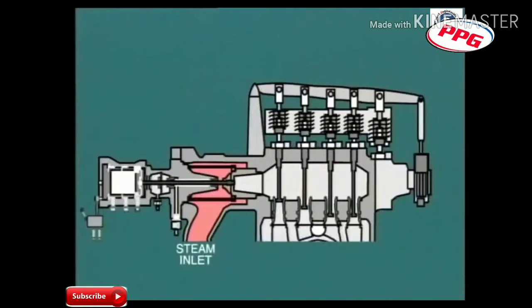In most arrangements of this type, a stop valve is fitted at the entrance to each steam chest. During normal operation, the stop valve remains in the wide open position, while the control valves are modulated to adjust steam flow.